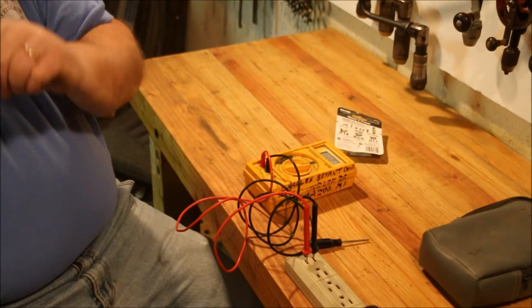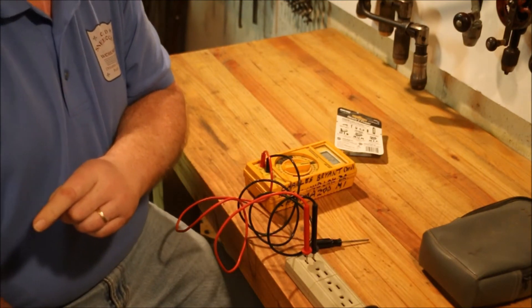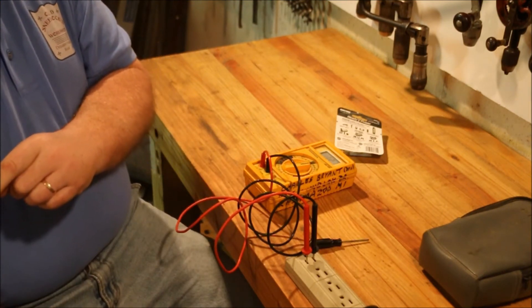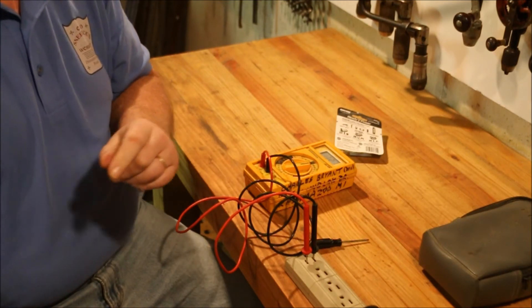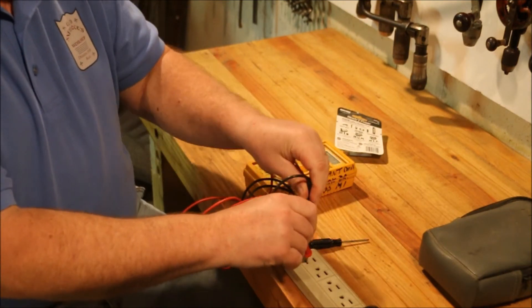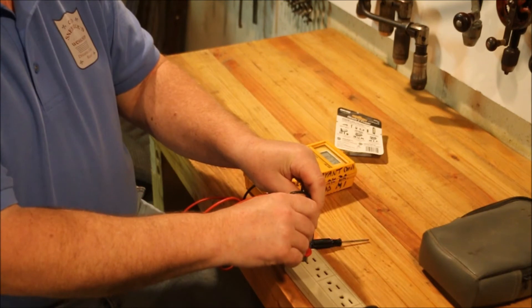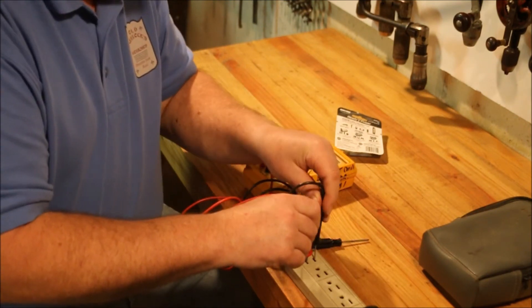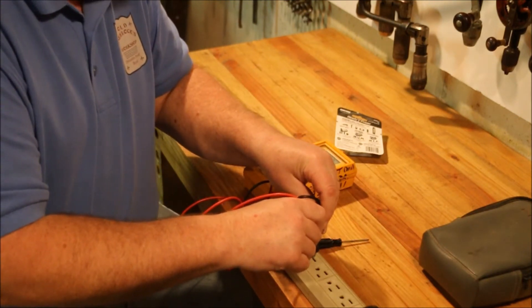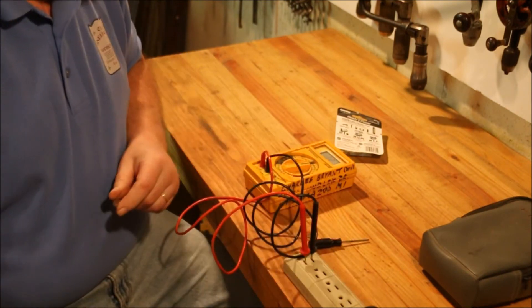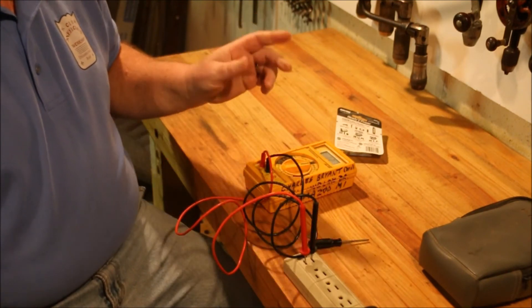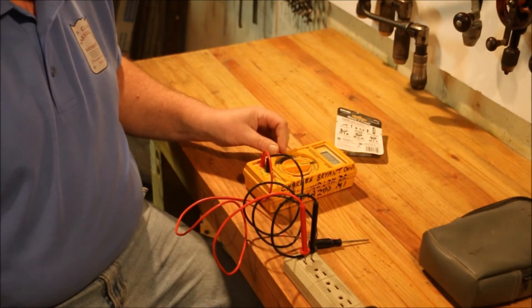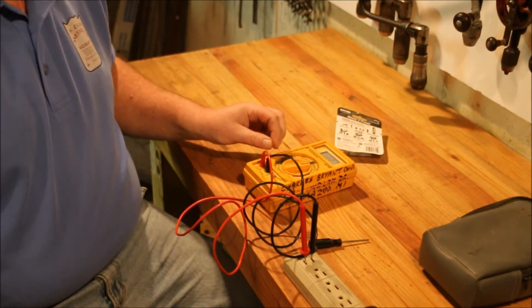But the ground is not a very good ground. I'm going to have to check out this circuit because it's showing 74 volts to ground. And I should have 121 just like hooking onto the neutral.